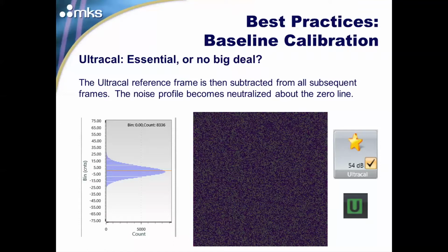So this purple and gray contrast shows really, really fine changes in signal. So if the bias of your baseline starts shifting positive or negative, say like your air conditioning or your heating turns on in your lab, and now all of a sudden the silicon response changes a little bit, you'll know that it's time to ultracal again. The status bar indicator will turn green.